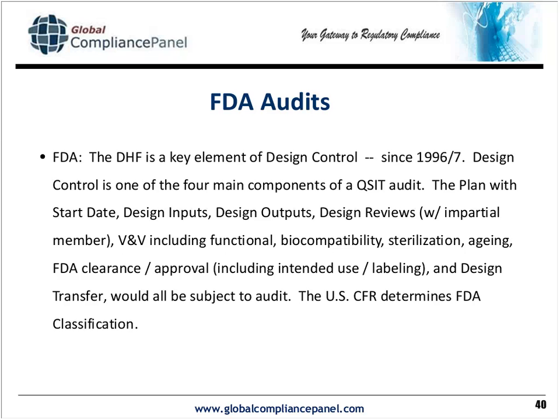I mentioned the classification, the differences between there. The FDA determines that, and they will check your product code, which is 3 alpha characters that have no bearing. They're arbitrary. Somebody told me at the FDA one time that they were initials of the original reviewers. I don't know if that's true, but nevertheless, they have no bearing to the product the product code covers.